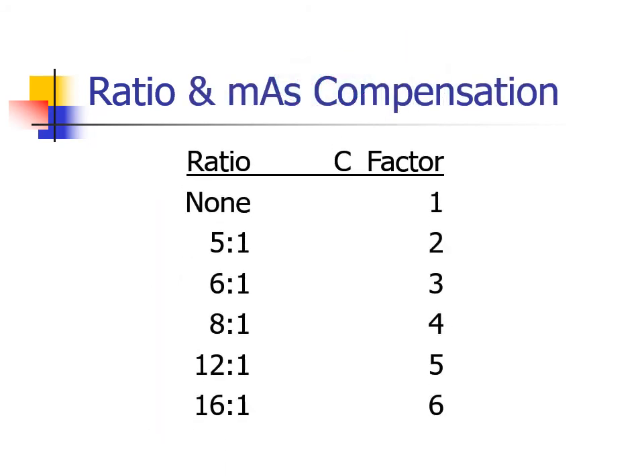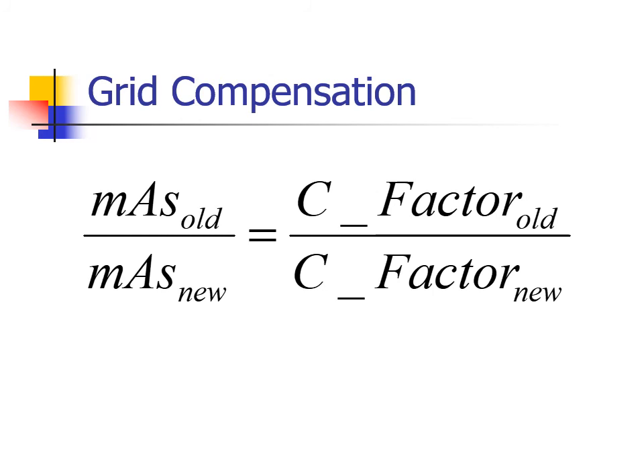Here is a table of common grid compensating factors. If you were performing a view that required three MAS non-grid, and you opted to perform it using a twelve-to-one grid, you would need to raise the MAS to 15 to maintain the same amount of radiation measured at the image receptor. This formula can be used to compensate from one grid to another. It might be used to compensate a technique that works in a table bucky that uses a twelve-to-one grid, to a portable technique where a six-to-one grid might be more appropriate.